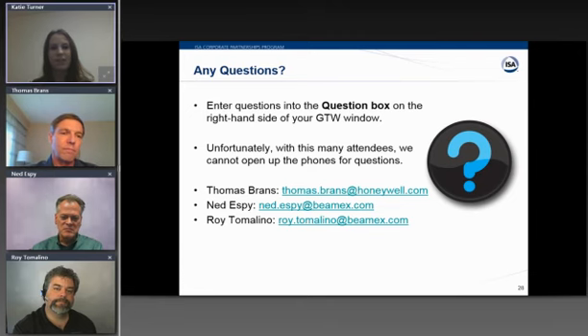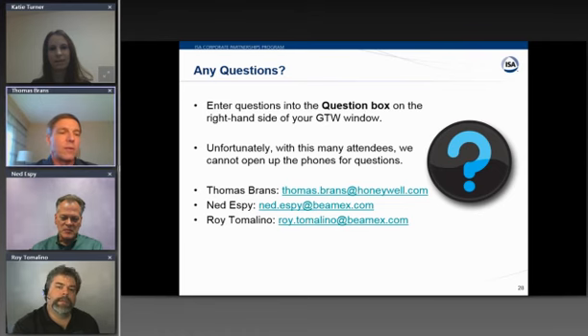Good enough. Next one. How do we offset an error on a temperature transmitter after calibration? How do you offset an error after calibration, on the sensor itself and not an offset in the DCS? I'm not sure I'm understanding that question, but I'll give it a go. So if you've checked the transmitter and in fact it needs to be calibrated, so it's been adjusted to agree with the standard, once you've calibrated, it's reading correct when compared to the standard. And then if you want to put in an offset, I think the way to do an offset really is to set up the range to accommodate that offset.